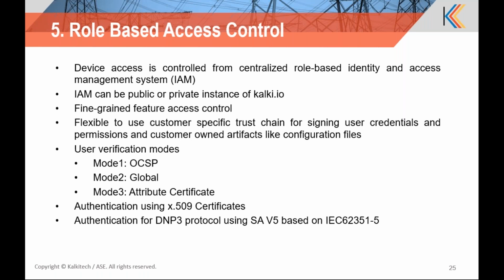And DNP3 protocol, if we use DNP3, SAV5 will be used based upon 62351-5 for authentication of authorization of selected actions, like controls, monitoring data, everything can be selected separately in the secure authentication. So protocol-wise function can be further drilled down using this thing.